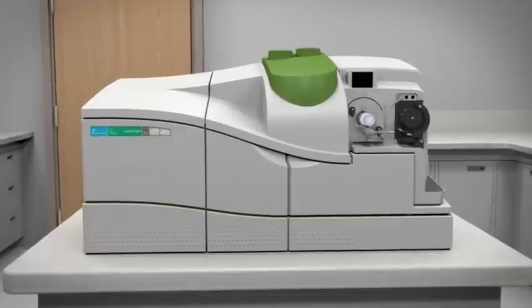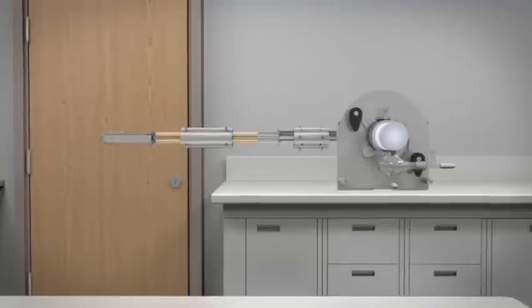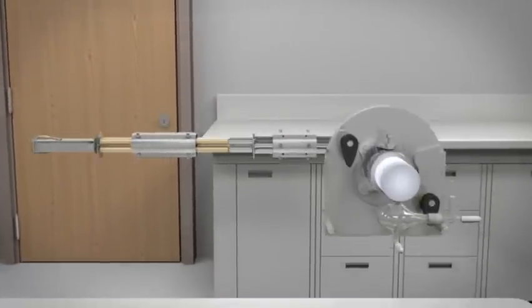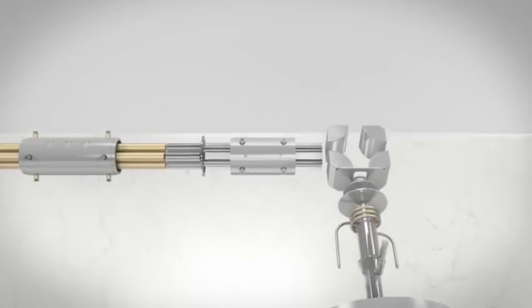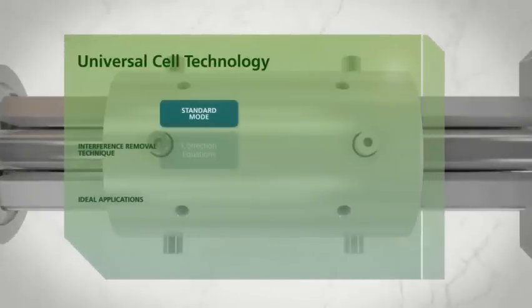For the first time ever, a single ICP-MS instrument offers both the simplicity and convenience of a collision cell and the exceptional detection limits of a true reaction cell. This universal cell technology allows analysts to choose the most appropriate technique for a specific sample or application.